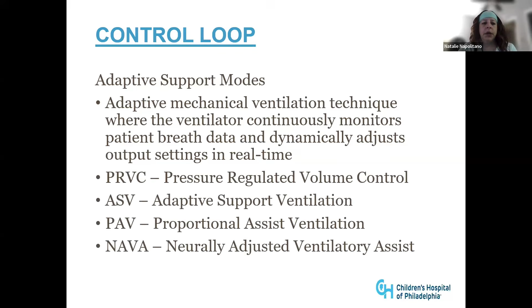The PRVC that I had just talked about is pressure regulated volume control. It's really a pressure breath, but it's reading the tidal volume. It's looking at your last two breaths and what that tidal volume was. And if I said I wanted a tidal volume of 50, but it's giving me a tidal volume of 20, it's going to increase flow and increase pressure until I can get that tidal volume. Adaptive support ventilation is similar. It adjusts the respiratory rate and the tidal volume to maintain a targeted minute ventilation.